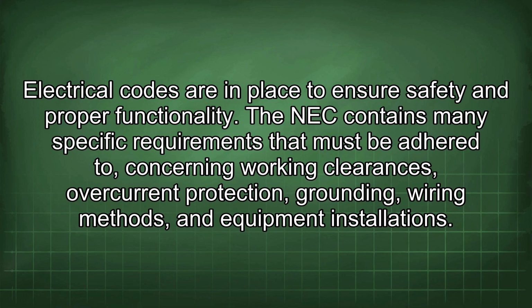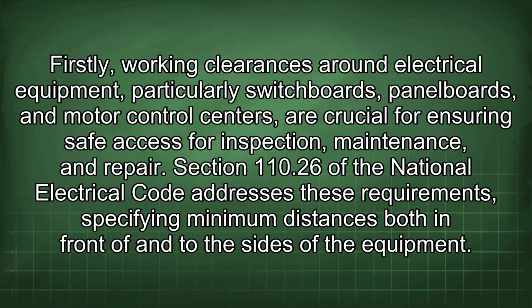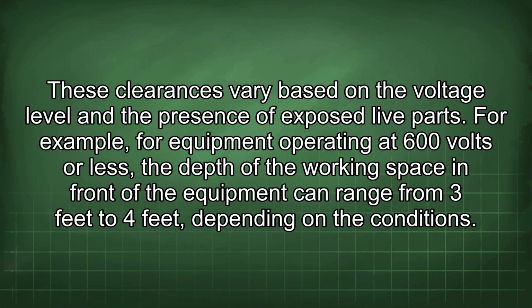The NEC contains many specific requirements that must be adhered to concerning working clearances, overcurrent protection, grounding, wiring methods, and equipment installations. Firstly, working clearances around electrical equipment, particularly switchboards, panel boards, and motor control centers, are crucial for ensuring safe access for inspection, maintenance, and repair. Section 110.26 of the National Electrical Code addresses these requirements, specifying minimum distances both in front of and to the sides of the equipment. These clearances vary based on the voltage level and the presence of exposed live parts.